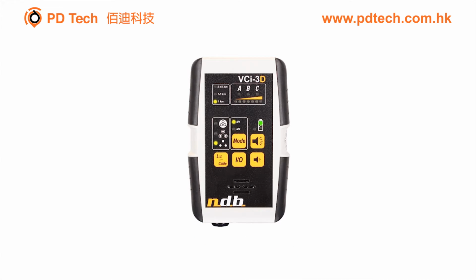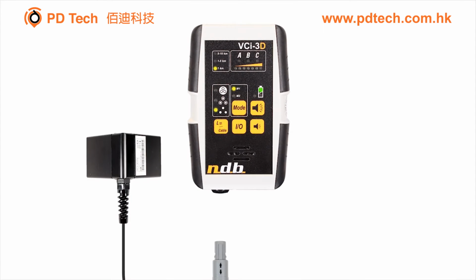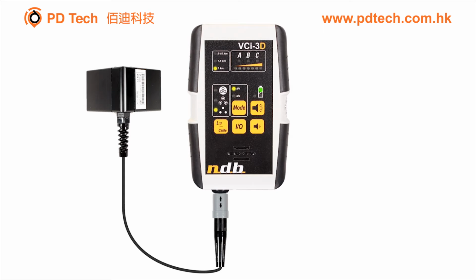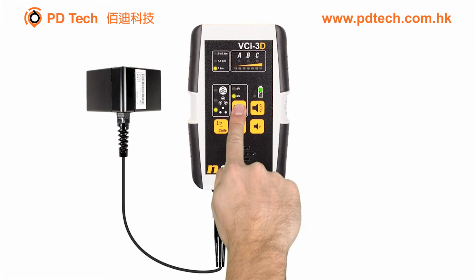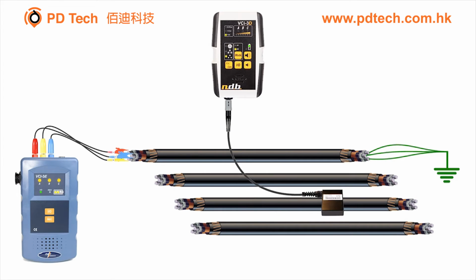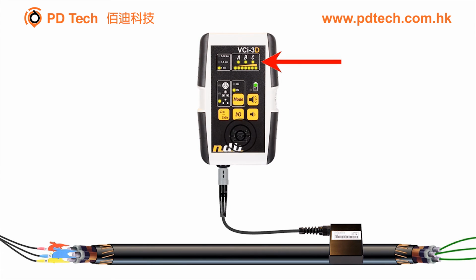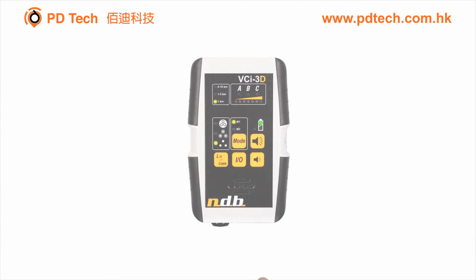The operator may need to identify a cable in a trench containing multiple power cables. In case where we have paper-lead impregnated cables, connect the VCI-3 SV high sensitivity sensor to the detector unit. For this application, Mode 2 should be selected on the detector. Apply the sensor on different cables found in the trench. In Mode 2, Cable ID mode, applying the sensor on the cable will have the A, B, and C LEDs turn on, and the voice message will be played back. Again, the detector's gain may be adjusted as needed.